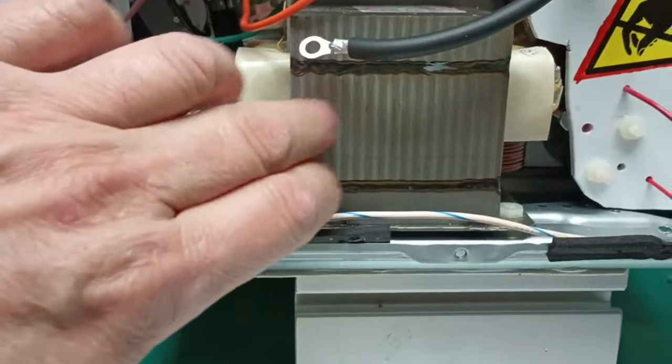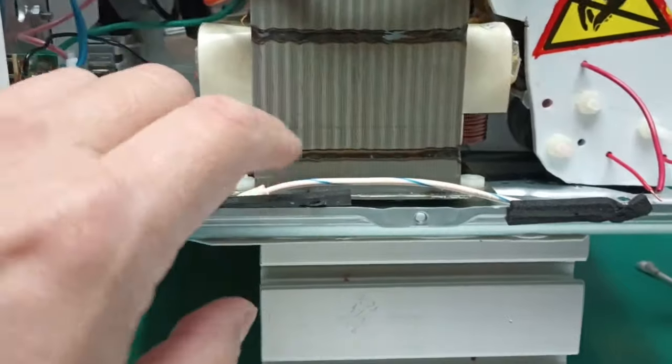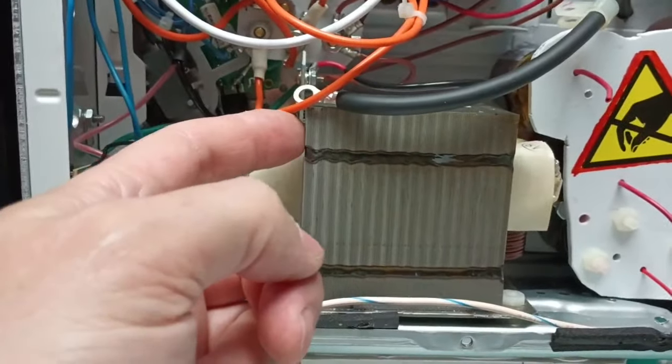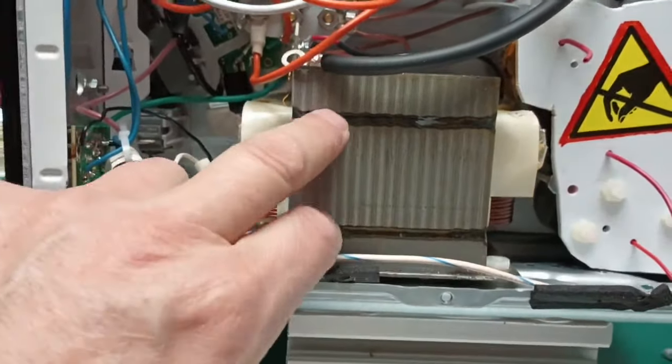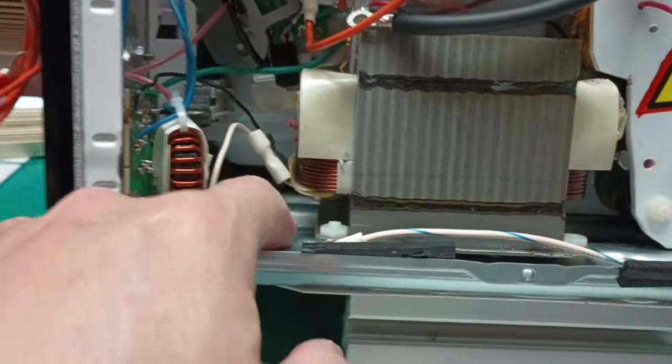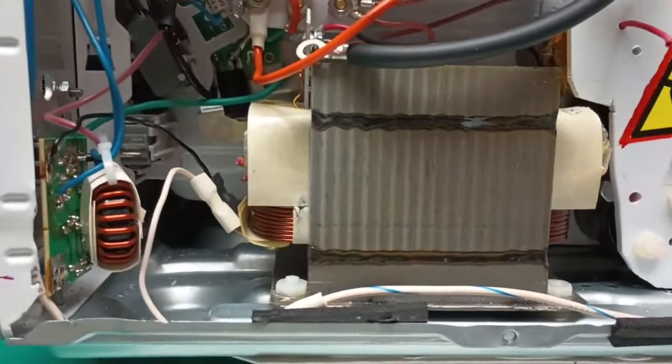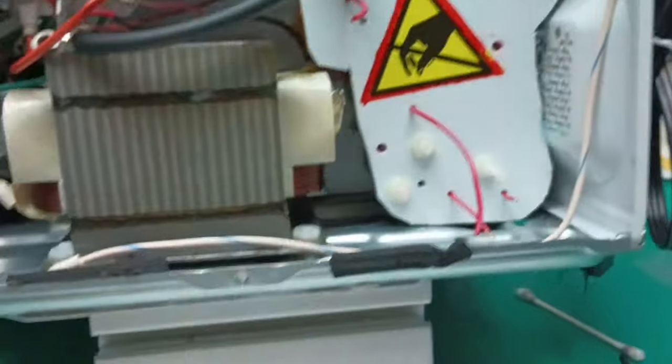Well, that's really not this winding. When this ran, this winding didn't vibrate. And somebody has made up the myth on one of these websites that welding this causes a core to short and makes it inefficient. That's simply a bald-faced lie. That's done for automation. Otherwise, there have to be holes drilled in each corner and bolts put through. And when those bolts are tightened, it does effectively the same thing as welding. It electrically ties all these plates together. This is done for automated manufacturing and it's done to keep vibration to a minimum. But this is a half-wave voltage doubler supply and it's both DC and AC and therefore the buzz. And it would be very expensive in production to do this to make it nice and quiet.